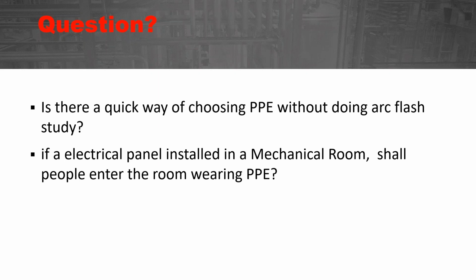and so suiting up might be warranted, especially if you're having to get into it where maybe it's a 208 volt panel and normally it might be a category 1 under normal circumstances. As long as the parameters in those tables have been met, then why not possibly wear category 2 or even category 4 PPE when getting in and or testing for the absence of voltage in this panel.